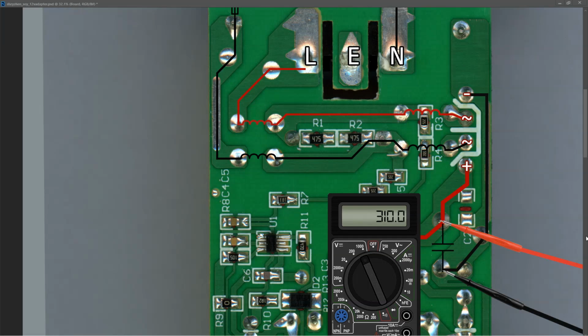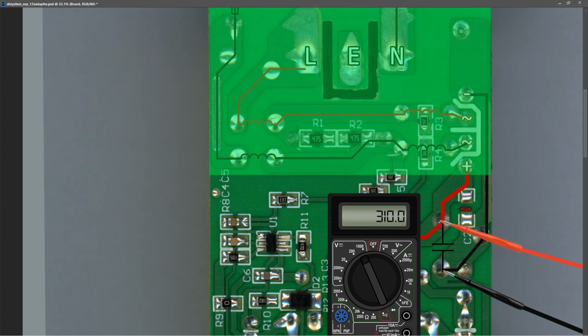Measuring in high voltage DC at that large capacitor, I also measured 310 volts DC. What does that tell us? If we have a very stable 310 volts DC that's not flickering up and down, staying pretty much bang on 310 volts, that tells me our whole input section here is good.